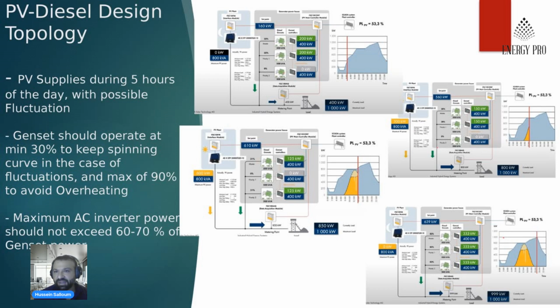But in case we don't have a lot of variability in the load, we can have one generator, but it's always preferable to have it multiple. Moving forward to, let's say, 2 p.m. in the afternoon, where we have around 850 kilowatt of load, we will have around 600 kilowatt of solar input, and the balance 125 kilowatt from the generators, two generators.